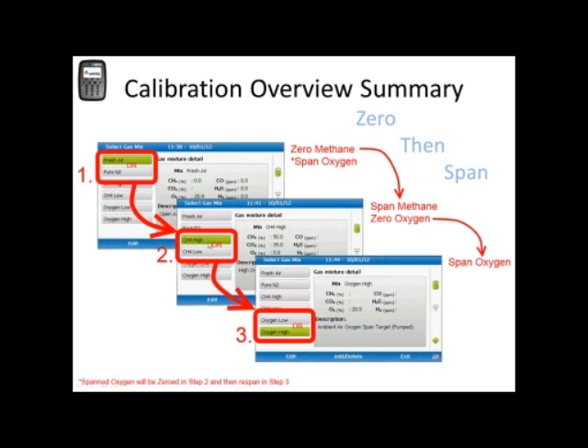that the user has available to select from: CH4 high and CH4 low. Once step 2 is completed, we jump into step number 3, which is the final step, to calibrate the oxygen gas mix. Again, you have 2 mixes to select from: oxygen low, which calibrates the oxygen to 4%, and oxygen high, which calibrates the oxygen to 20.9.